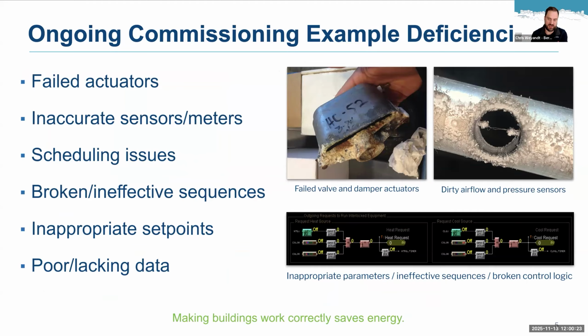We very regularly find that basic HVAC system maintenance generates significant savings. So fixing failed valve and damper actuators, dirty airflow sensors, is something that was sort of surprising to us. On exhaust air systems where we use hot wire anemometers for monitoring airflow, these systems can get very dirty and underreport the amount of airflow, which can dramatically increase the air change rates in our buildings due to dirty sensors. All it takes to solve that problem is a Q-tip and some isopropyl alcohol, and they generally work just fine after that.